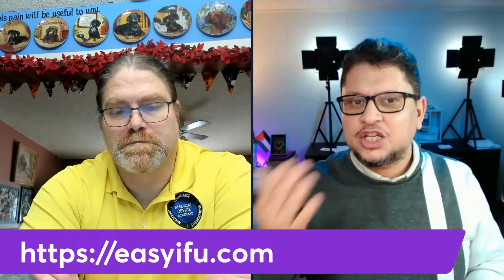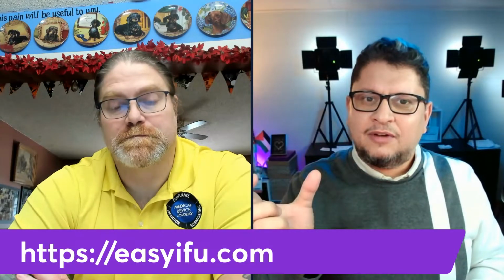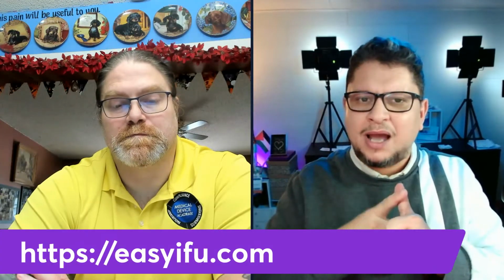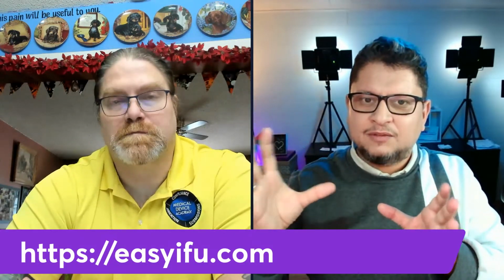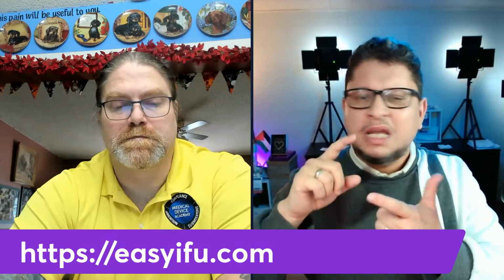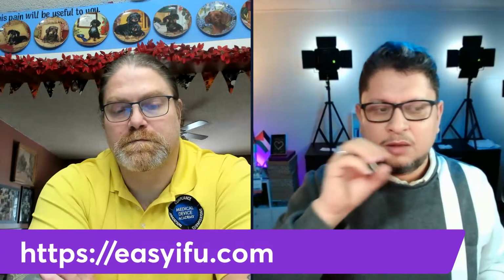And the additional thing that I didn't tell you about EZ IFU is that there is also a module for the creation of the label, which means that you will arrive at the label section. Now you'll create a label for this product that we are talking about. So you have to answer a lot of questions. Is my product sterile? Does my product have a measuring function, is it IVD, etc. And then it will place all the symbols from the ISO standards. Then automatically it will place your legal manufacturer symbol with the name of the legal manufacturer. If you have an importer or an authorized representative, all the information will be there. Even the UDI code, they will place that there.